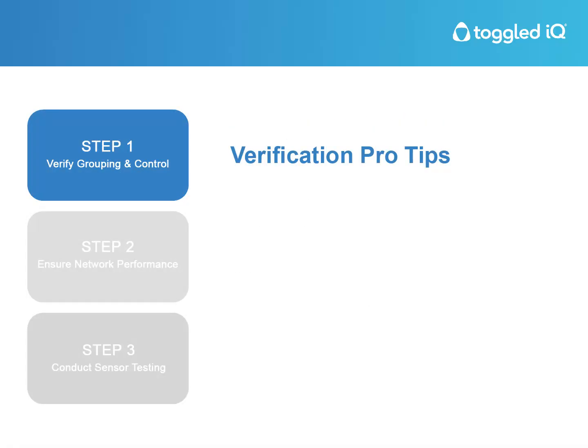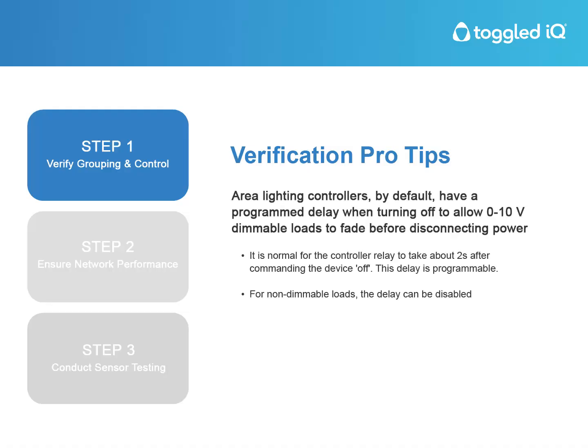Verification Pro Tips. Area lighting controllers, by default, have a programmed delay when turning off to allow 0 to 10 volt dimmable loads to fade before disconnecting power. It is normal for the controller relay to take about 2 seconds after commanding the device off. This delay is programmable. For non-dimmable loads, the delay can be disabled.